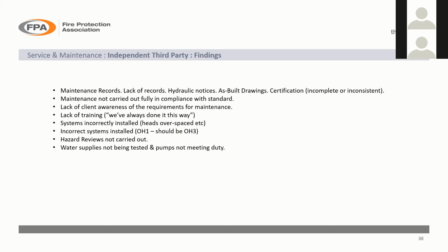And that's not always the case, to be honest. So you need to test them, and also you need to test them if you've got duplicate water supplies coming in from a town's main. You need to test them one at a time and not both together, to make sure that if one of them is isolated, you've still got enough water to meet the requirements of the system. So I've just covered that.